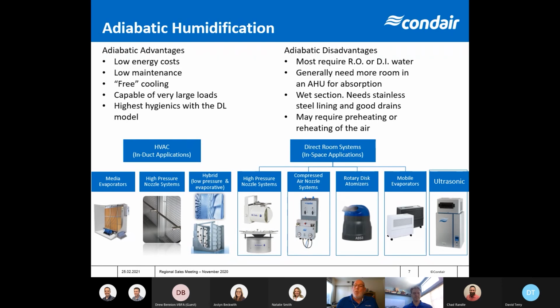We generally need more room in an air handler for absorption. So we could talk about that a little bit. Both our ME, our evaporative media, and the DL systems, we like to have about 36 inches of room within the air handler for these systems to operate. With the high pressure nozzles, the HP, we need about 6 feet of room in an air handler. So that's a consideration as well. And we talked about, due to the large cooling that we generate, we may need to do some preheating or reheating of the air.